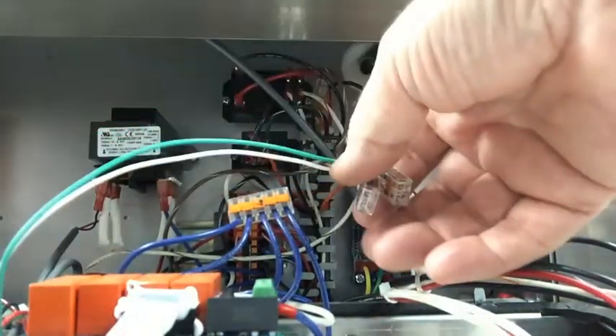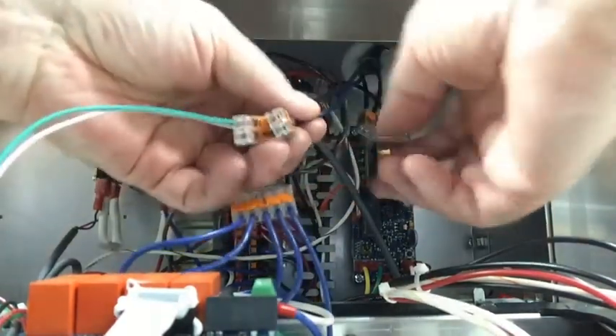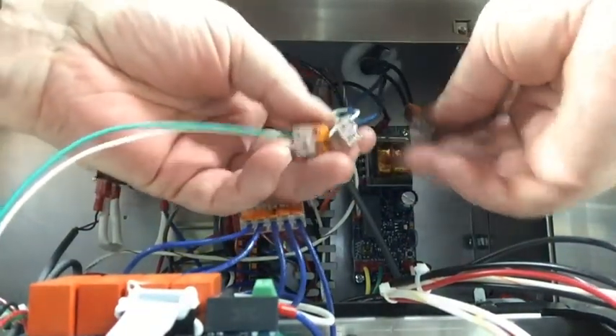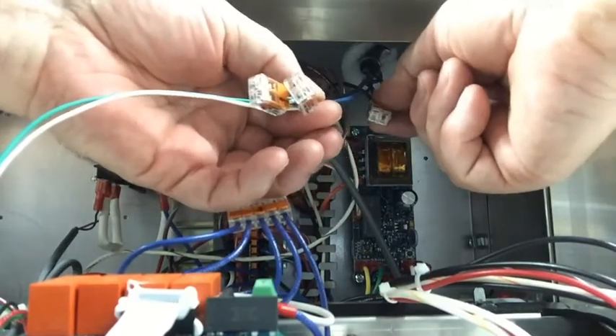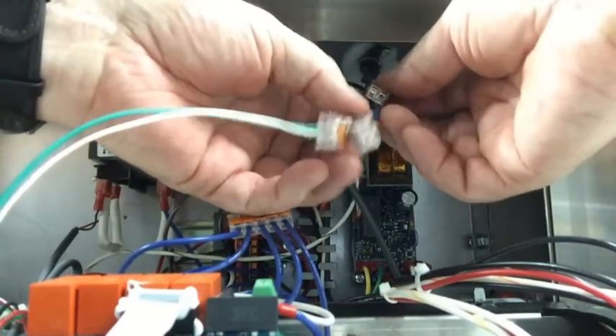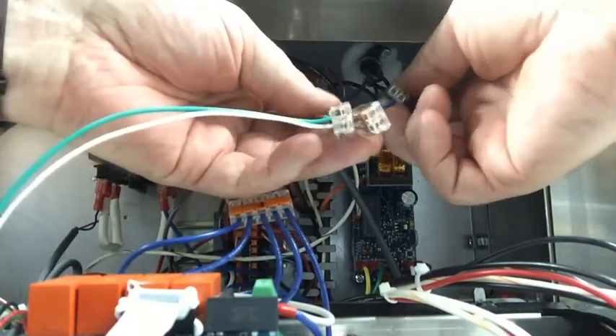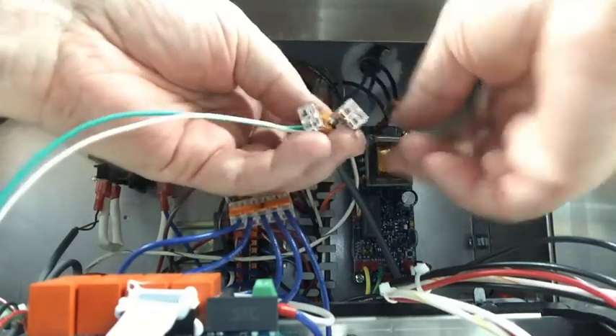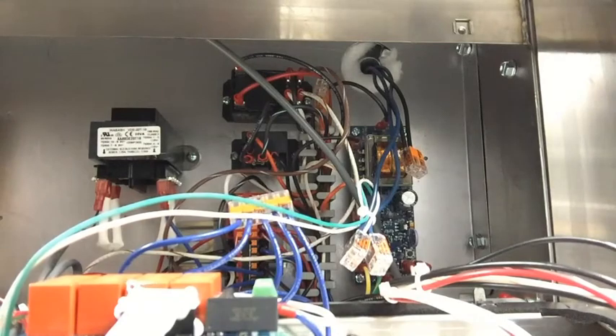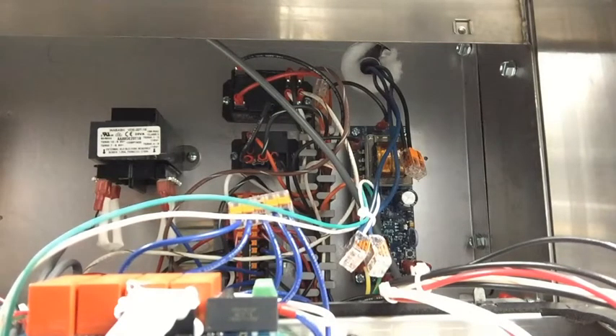So if you think you have a drain switch error and you can't figure out which one it is, you could take these 2 right here loose and then ohm them out from here and check black to blue and see if you're getting a closed circuit. And you should be getting 2 closed circuits. They're actually wired in series so that if either one of them is open, it will give a drain open alarm to the controller and not let it heat.